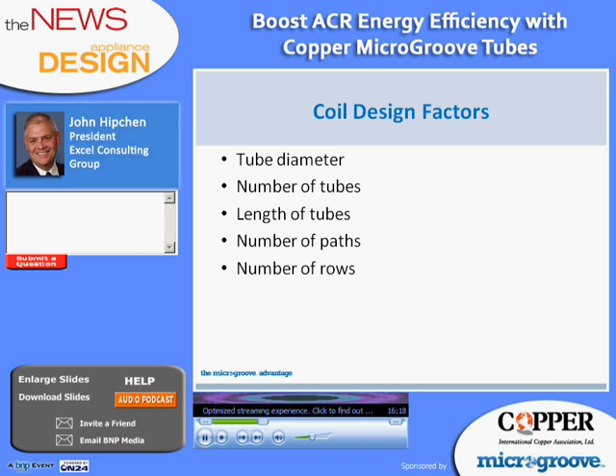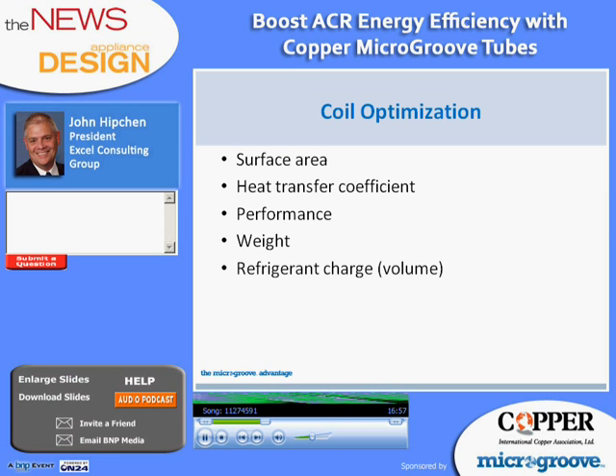There are a number of factors that a heat transfer engineer can look at when re-engineering refrigeration and air conditioning coils. The factors that we will focus on over the next few minutes are the tube diameter, the number of tubes, the total length of all the tubes in the coil, the number of tube rows in the coil, and the number of paths that the refrigerant can take as it passes through the coil. A change in any or all of these factors can affect these coil parameters and measurements. We call this set of criteria coil optimization, because the goal of an exercise such as this is to find a set of design factors that provides a more efficient, more compact, and less costly coil. A quote-unquote optimized coil design, if you will.